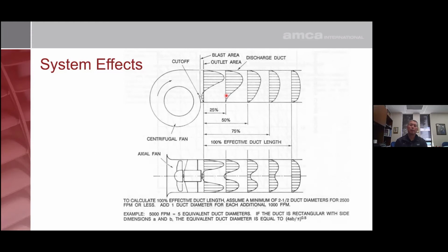If you're moving only 1,000 feet per minute, it's not quite as critical because it's a squared value. So it's going to be 1,000 divided by roughly 4,000 squared, so that regain is going to be much less. But the faster the velocity, the more pressure you're going to lose from that fan during operation. And that pressure is lost forever. You're not going to be able to get it back, other than running the fan faster, and running the fan faster means you're going to consume more brake horsepower and your energy costs are going to start going up that way. Does that answer the question?